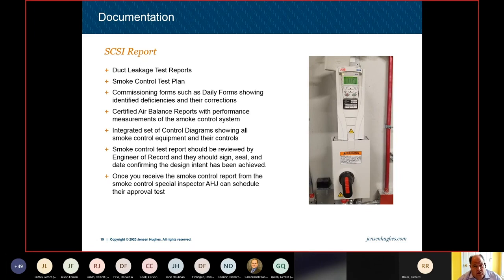And really why those things are so important, we'll see this in a little bit when we start talking about inspection, testing, and maintenance of existing systems. The more that's laid out in one combined set, so you don't have to go through 10 different drawing sets, you don't have to run to a mechanical set and a fire alarm set and an electrical set to pull together the information. All that's pulled into one combined control diagram set that shows you everything involved in smoke control on one set of drawings.